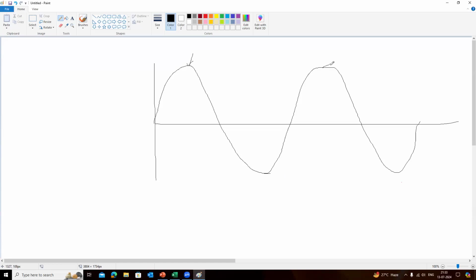It is not possible to select this when you are performing the short circuit using the 60909 standard. That means when you are doing the short circuit study in ETAP, you will not be able to change the instant at which the fault has occurred. What I mean is, if you take the sinusoidal wave here, whether the fault occurs at this instant, or at this instant, or at this other instant, you will not be able to change that when performing short circuit studies using ETAP.